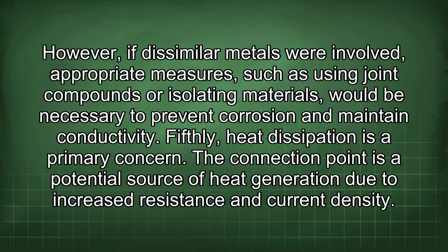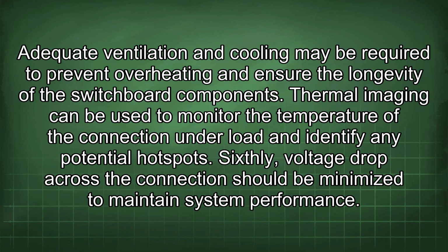Fifthly, heat dissipation is a primary concern. The connection point is a potential source of heat generation due to increased resistance and current density. Adequate ventilation and cooling may be required to prevent overheating and ensure the longevity of the switchboard components. Thermal imaging can be used to monitor the temperature of the connection under load and identify any potential hotspots.